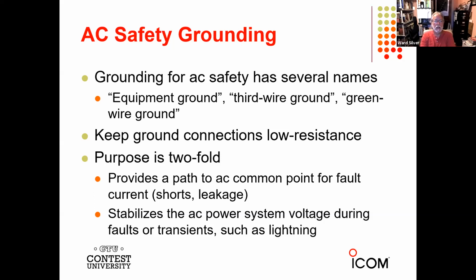The purpose of this connection is twofold and twofold only. It provides a path back to your AC common point for fault currents. That's short circuits and leakage. And so the idea is to give that current a path so that it can trip the protective components and they will remove power from your circuit. Leakage currents from compromised insulation or from excess capacitance also should go through the ground connection and not through you.